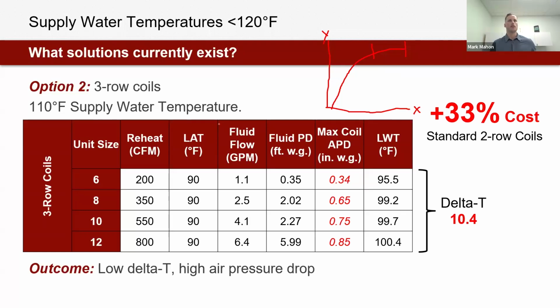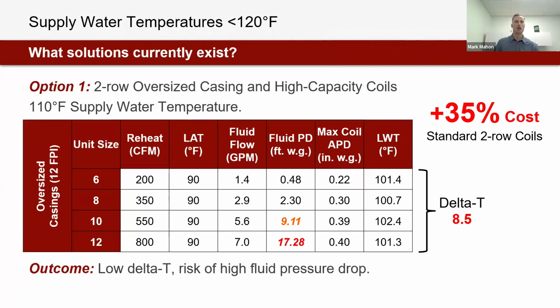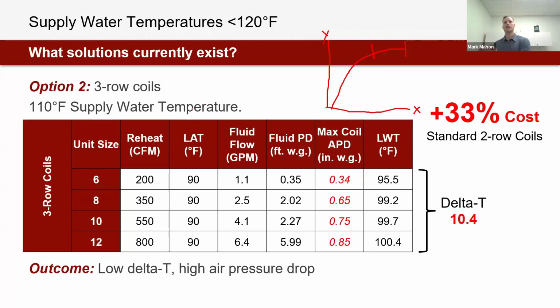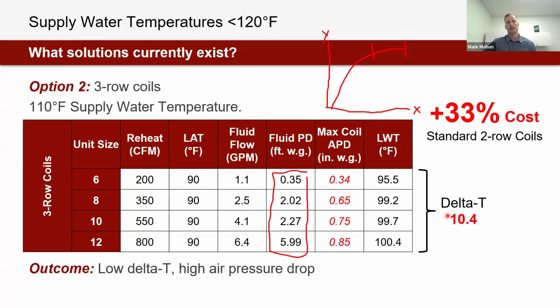And so, just to flip back for context, we had the 2-row oversized casing high capacity coil. What we might see instead would be a 3-row coil. And when we look at a 3-row coil, performance is a bit better. Fluid pressure drop is lower. We like that. Fluid flow rate is low, but we're going to start to see that air pressure drop for the coil creeping up. And I don't love the idea of making the boiler efficient just to shoot the air handler in the foot. In this case, yes, we get better hot water performance, but we're seeing a fan energy index that is getting worse and worse and worse. Once again here, the delta T is still not even that significant.